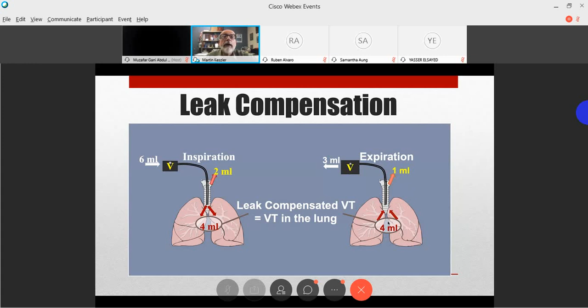But using the data that I showed you on the previous slide, they are able to give us this compensated tidal volume. With the Draeger VN500, they give you an option, and this was not available on the 8000. It is available in the VN500 and the newer models coming up. You have the option of activating or not activating the leak compensation. I can, for the life of me, not imagine why you would ever not want to activate it.